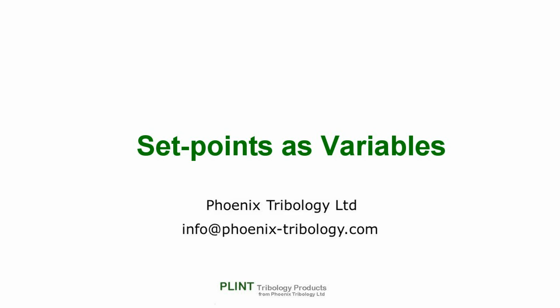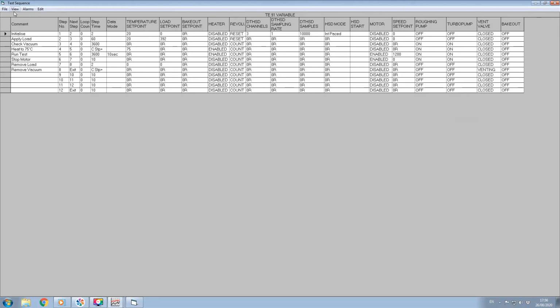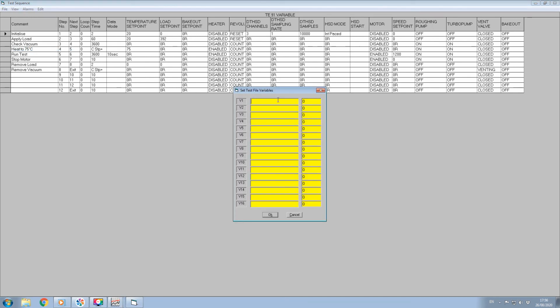You may want to run tests using a common test sequence, but with changes to a given control parameter. You could, of course, simply edit the test sequence file each time you wanted to change the parameter. Alternatively, the software allows the user to program a variable set point as opposed to a fixed value. The user is then prompted to enter the required value at the start of the test. To create variable set points, click on View on the Test Sequence File toolbar and select Variable Table from the menu. This generates a table for defining variable set points.